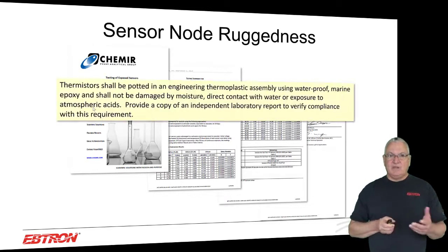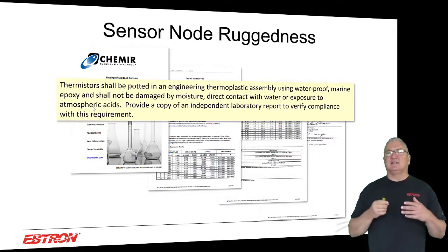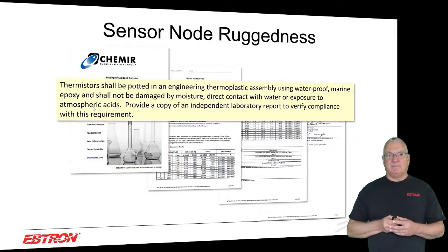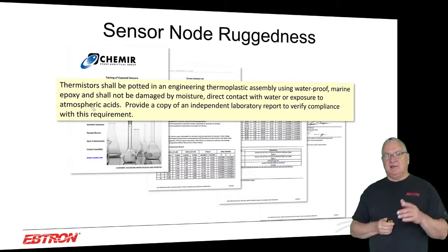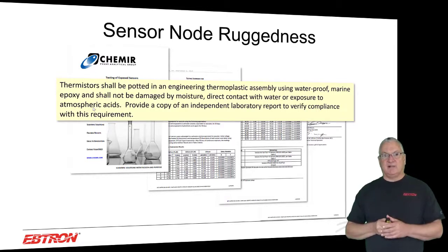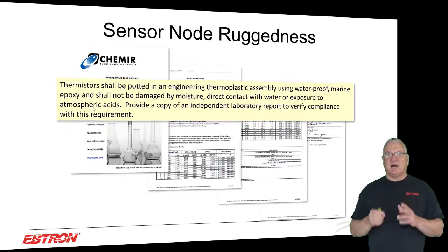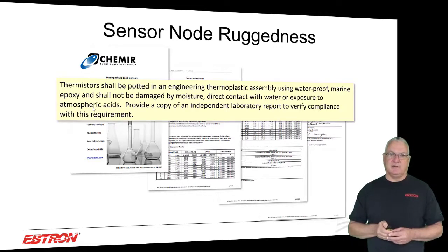So we suggest that you require this. Thermistors shall be potted in engineering thermoplastic assembly, that is definitely key to us, using waterproof marine epoxy. But the thing that's the most important here is it shall not be damaged by moisture, direct contact with water, or exposure to atmospheric acids, and provide a copy of an independent laboratory report to verify compliance with this requirement. Okay, we do a lot of things that our competitors don't do, all right, because we want to make sure you have long-term performance of our equipment.